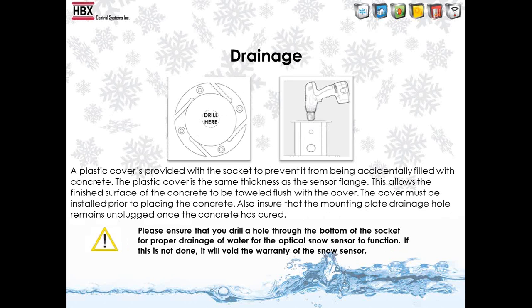Something we commonly see not being done is proper drainage for the snow sensor. What needs to be done is drill a hole through the bottom of the socket to allow any moisture or water that builds up inside to drain. If drainage is not done at the socket and it fills up with water and turns to ice, this can ultimately cause damage to the sensor.